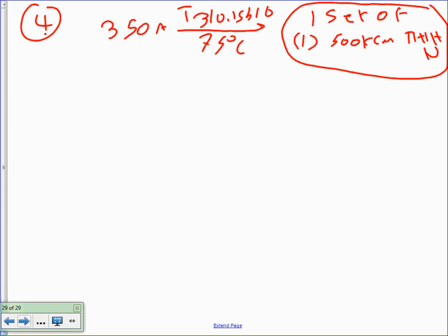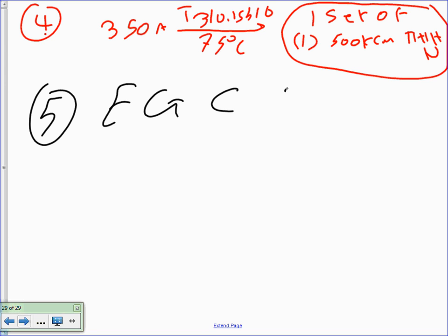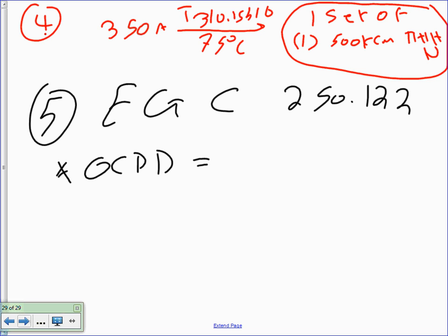Okay, the last thing, and then I'm done for good now. Equipment grounding conductor. This is your 250.122. Overcurrent protection device, what was it? What was it, 700? 450. Am I still stuck with the first one? 450, 450 amp. Then what do you do?